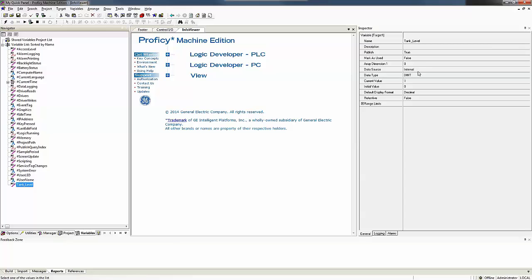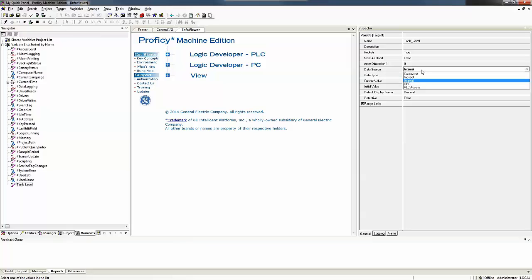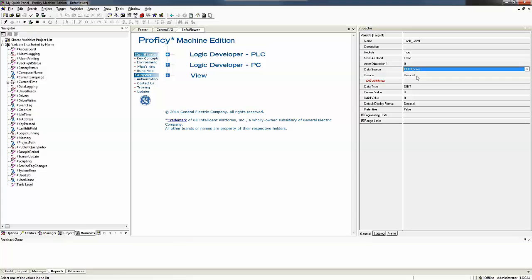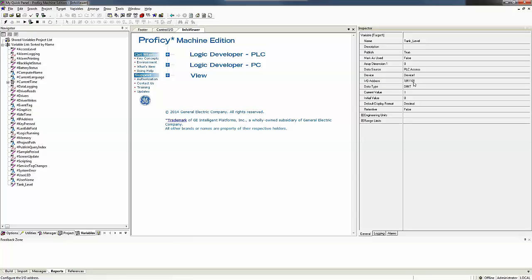So I've named my variable, but I want to pull a piece of data from my PLC. So I changed my data source from the default of internal to PLC access and it chooses device one for me. And it says what IO address in the PLC. The PLC programmer told me my level was located at %R1101 as my address. So now I have one variable created that's PLC access.